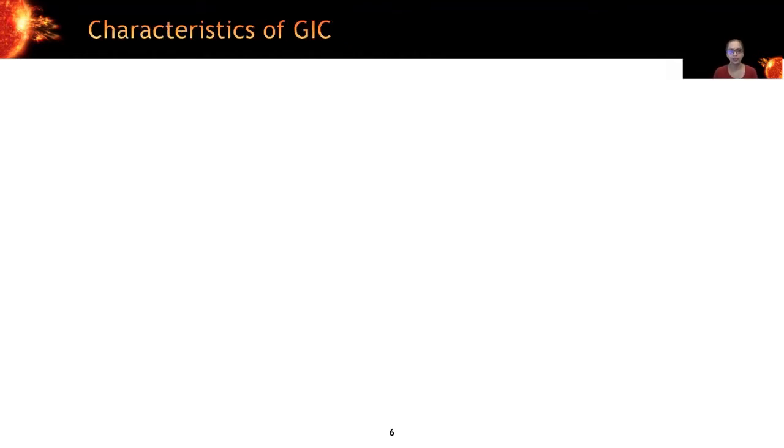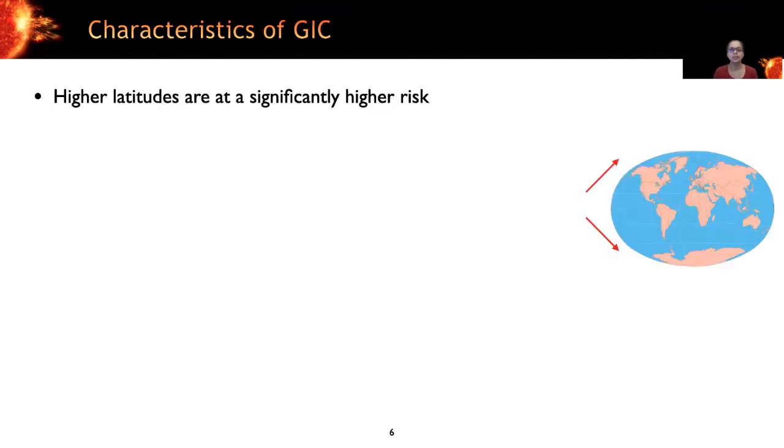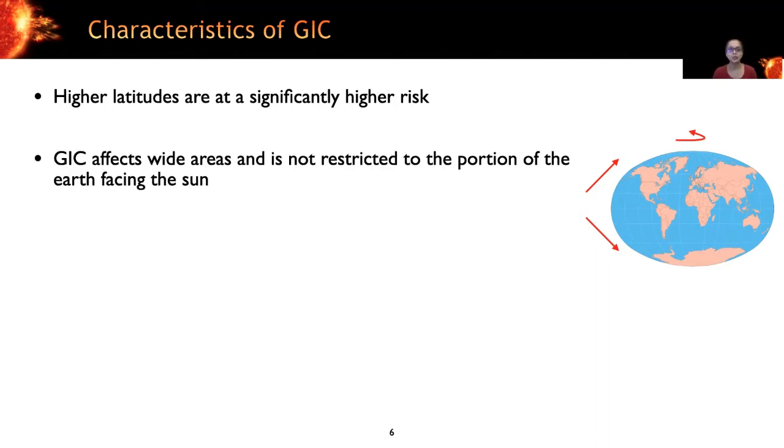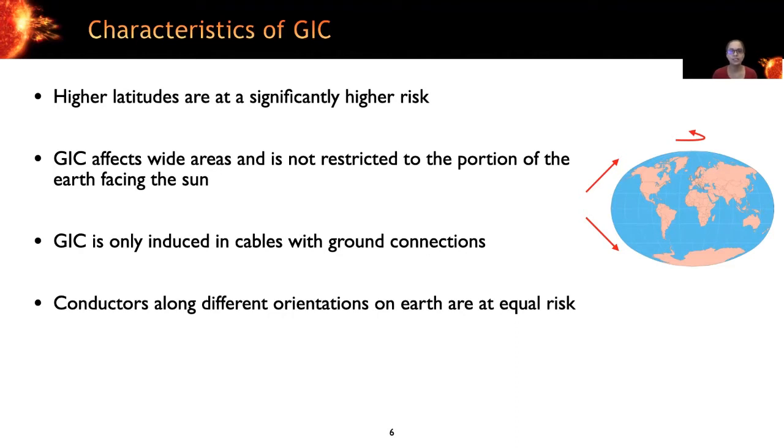Next, we'll see some characteristics of these induced currents to better understand the risk. Due to the orientation of the Earth's magnetic field, higher latitudes are at a significantly higher risk. And it's for the same reason that auroras are closer to the poles. The induced currents also have a much higher chance of being induced in the higher latitudes. Now, since the impact is caused by interactions with the Earth's magnetic field, the induced currents can affect wide areas across the globe and are not restricted to the portion of the Earth that's facing the sun. And GIC is only induced in cables, long cables with ground connections that are separated by large distances. So not all infrastructure components are equally vulnerable. And finally, conductors along different orientation on the Earth's surface are at equal risk. So in other words, north-south or east-west orientation of the cable does not matter.